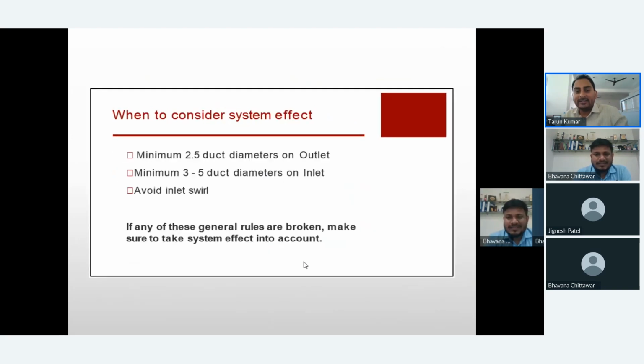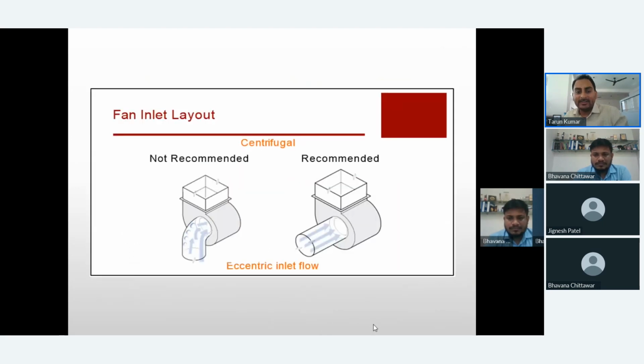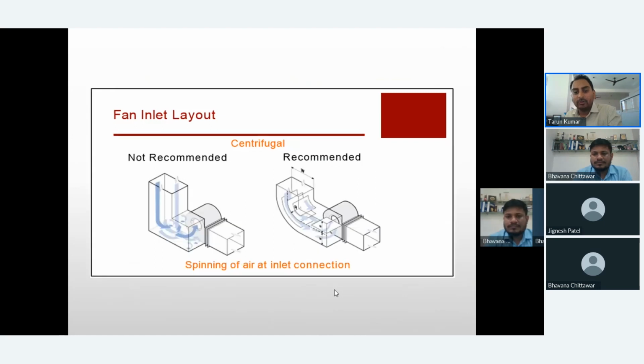As per AMCA, to avoid the system effect, a minimum of 2.5 duct diameters of straight duct should be there at the outlet, and a minimum of 3 to 5 times the fan size as duct diameter should be there at the inlet to avoid any inlet or outlet swirl. You can see the recommended and not recommended photographs. Here they have used a bend immediately at the inlet, which we have to avoid because it creates turbulence in the flow. We should always use straight duct there.